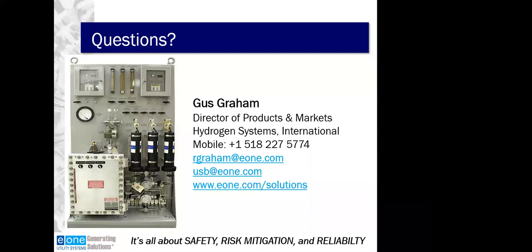So clients frequently perform a calibration with just one gas, which is H2. How does this affect the measurement? That's a great question. I'm going to assume one of my colleagues threw it at me because I forgot to mention that. Yes, calibration must be done with all three gases. That's because the design of the cells looks at all three gases, and we need to make sure that any drifting that's associated is captured for each of the phases, so each of the gases. So thank you for bringing that question forward. JL asked that question. So thanks, JL.